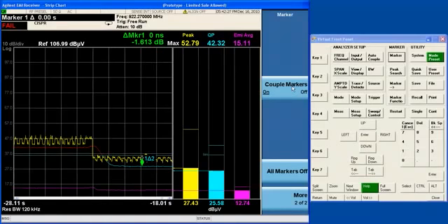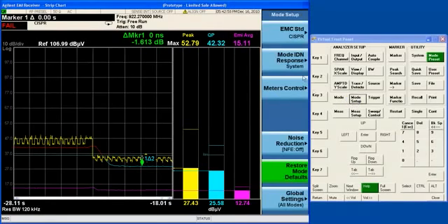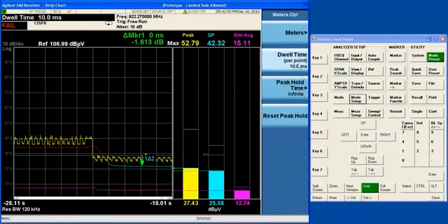So with the strip chart, you're able to get a lot more insight into what's going on in the time domain. And I should emphasize that this capture is gapless, that we hold off alignments while we're capturing, and any system interruption does not affect the fact that we're actually taking a data point as rapidly as the meters can function.